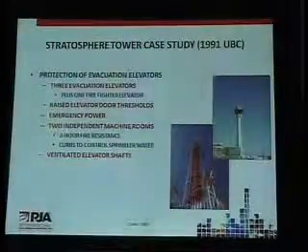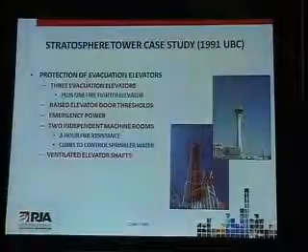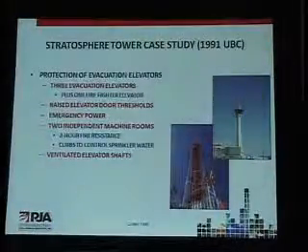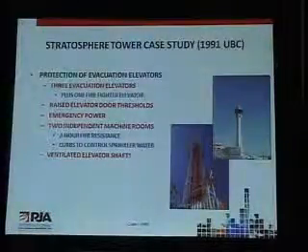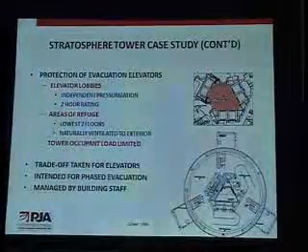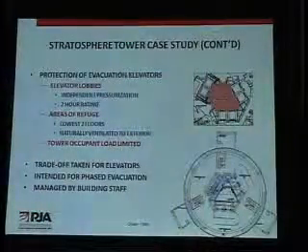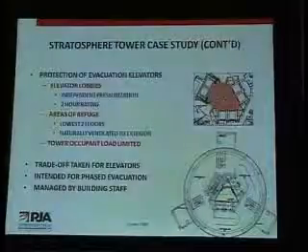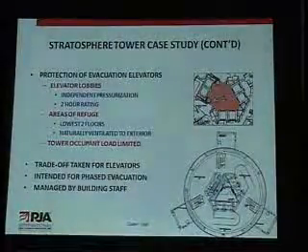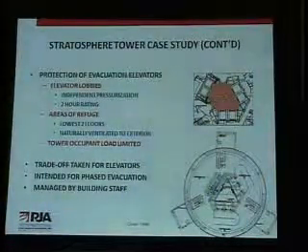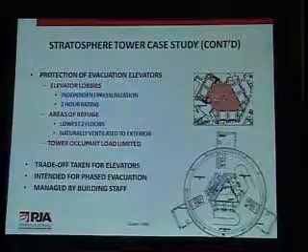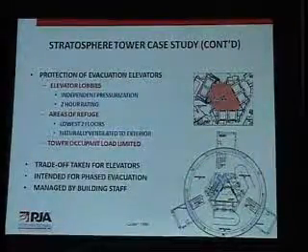There's 2-hour fire resistance. There's curbs to control sprinkler water going into machine rooms. The elevator shafts are ventilated from smoke. Here are some examples of the floor plans. The upper floor plan shows a typical floor with a rated vestibule. The vestibules have independent pressurization, as I mentioned, and a 2-hour rating.